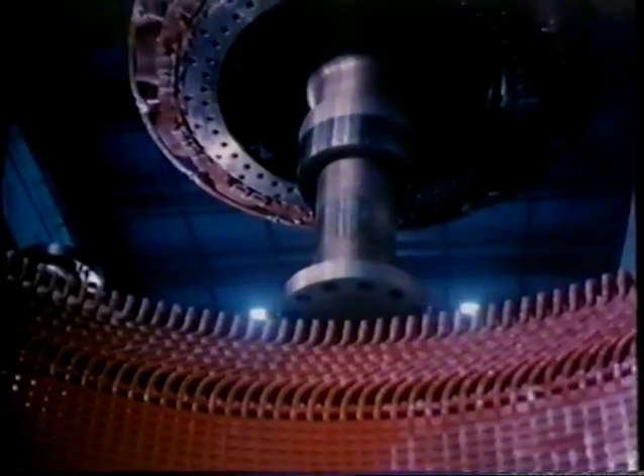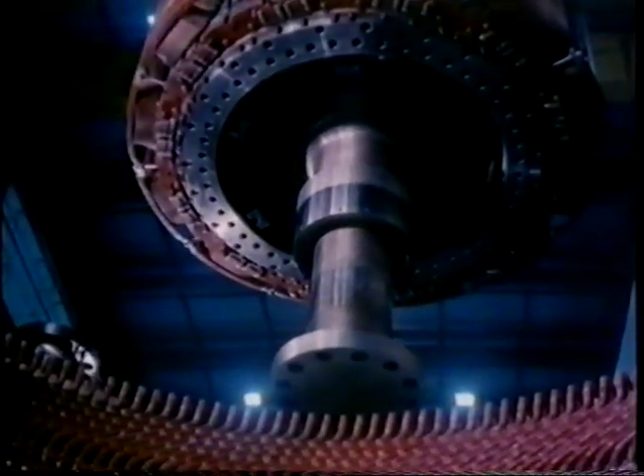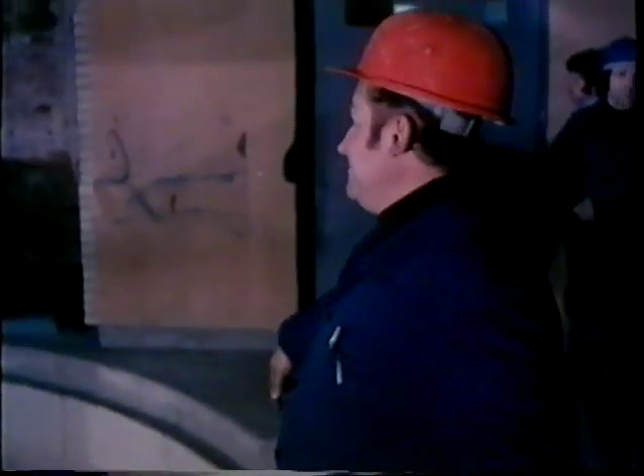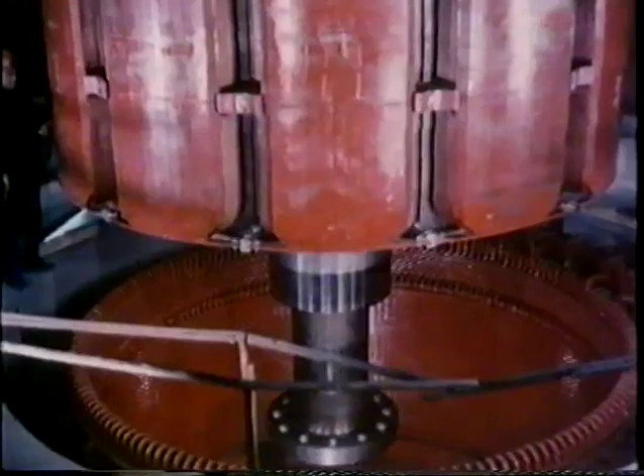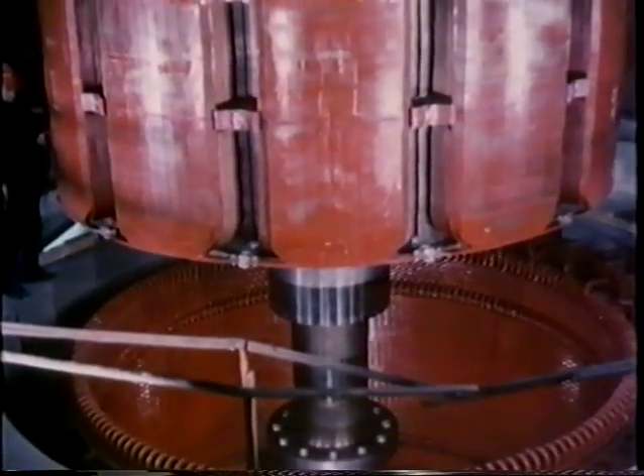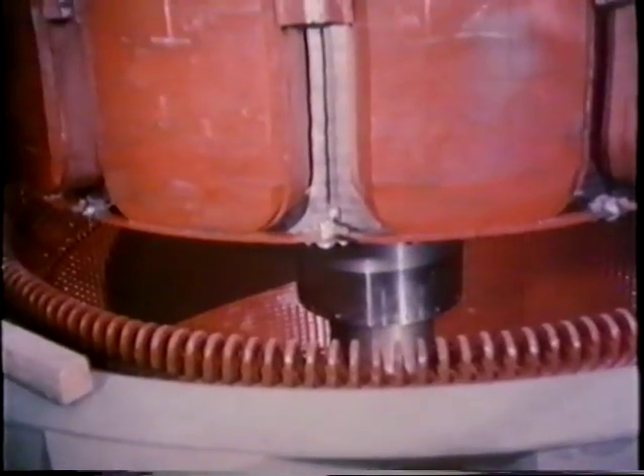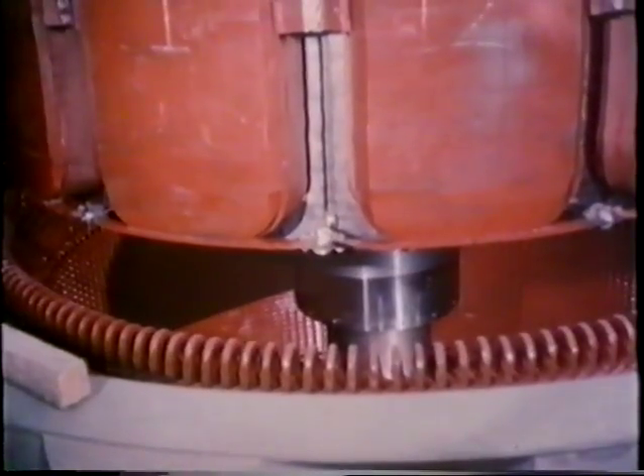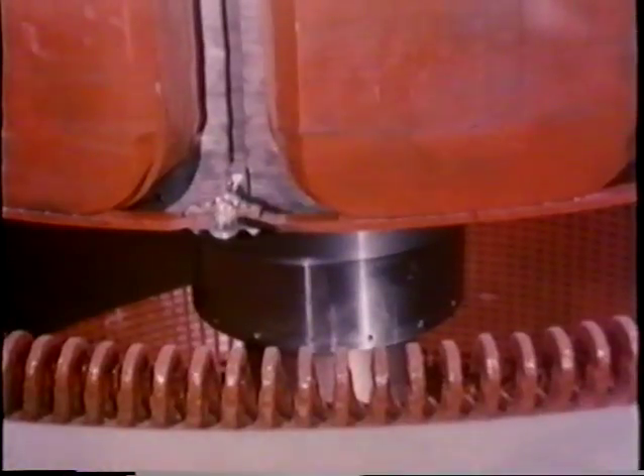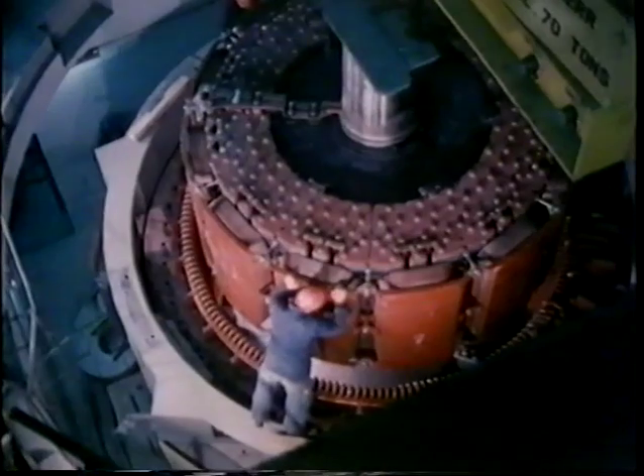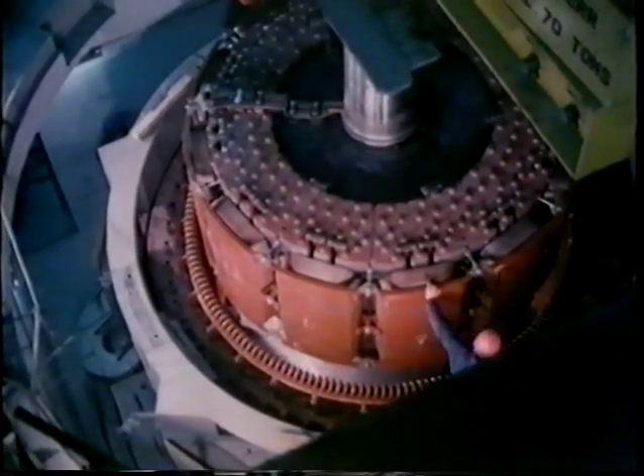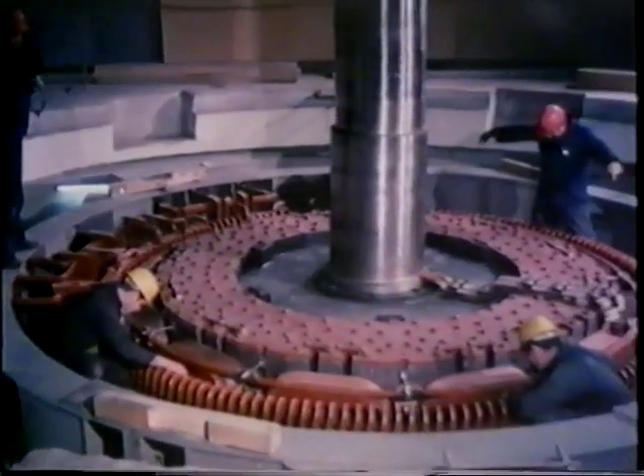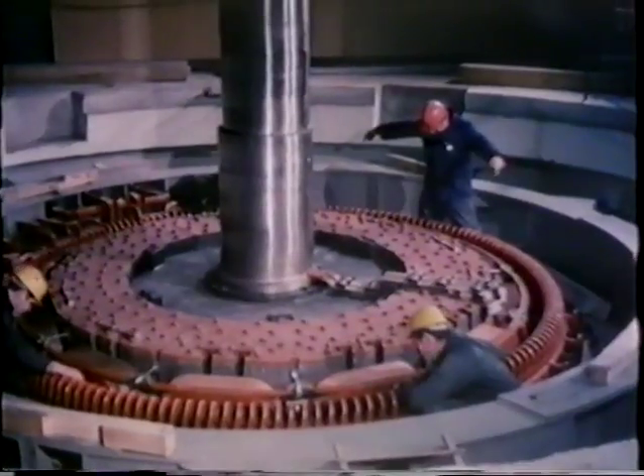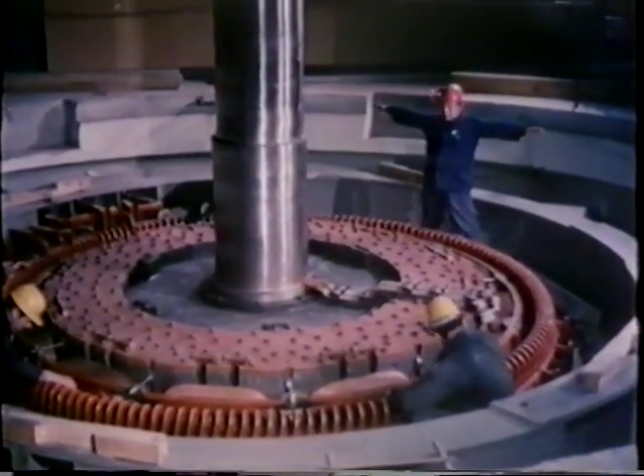The installation of the motor generator unit nears completion as the rotor is installed. Each unit has a rated output of 87.5 MVA as a generator at 0.85 power factor, and a rated power of 87.5 MVA as a motor at 0.95 power factor for maximum output. The rated voltage is 10.5 kV at the normal running speed of 500 RPM. The output for synchronous condenser operation at 0 power factor, under or overexcited, is about 70 MVA.